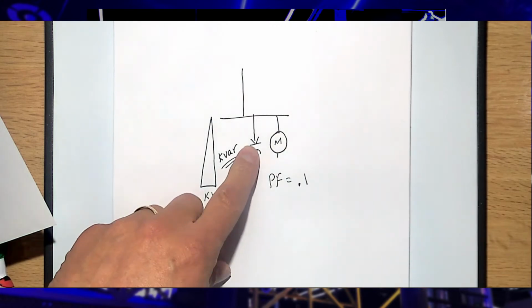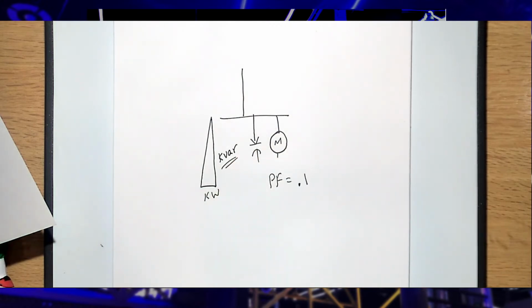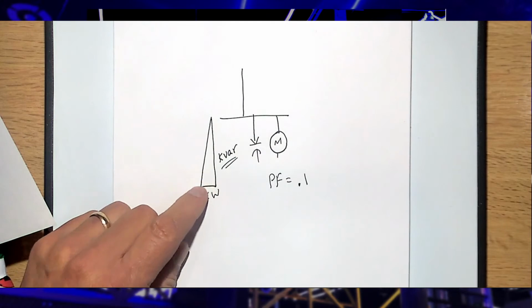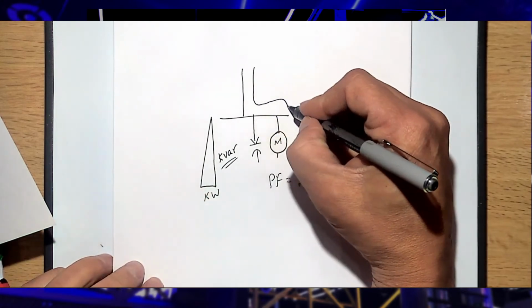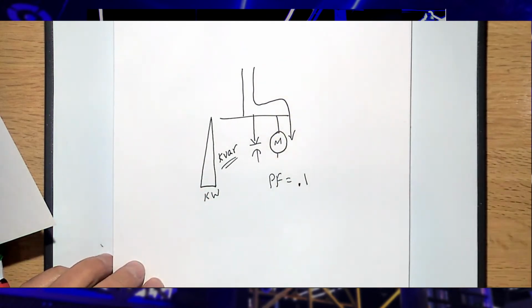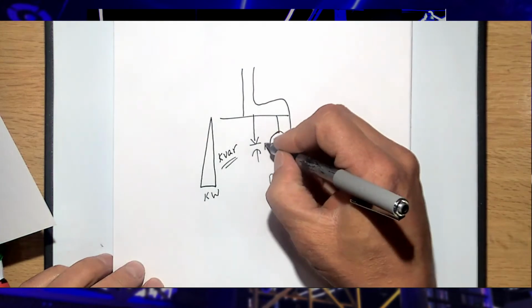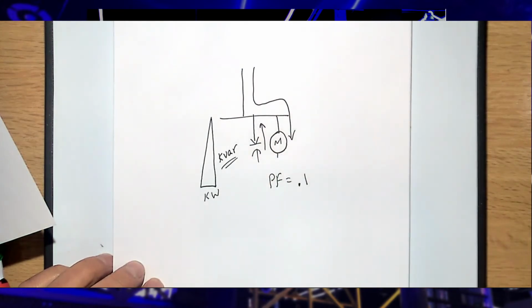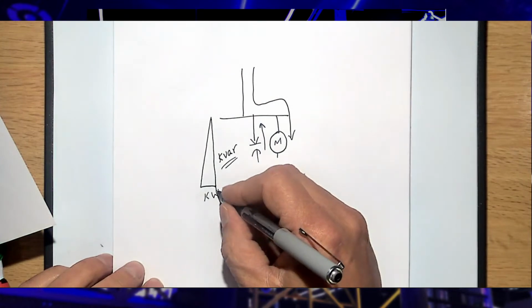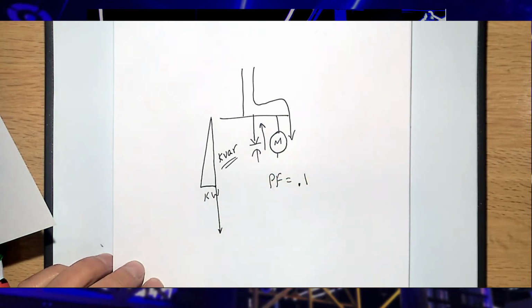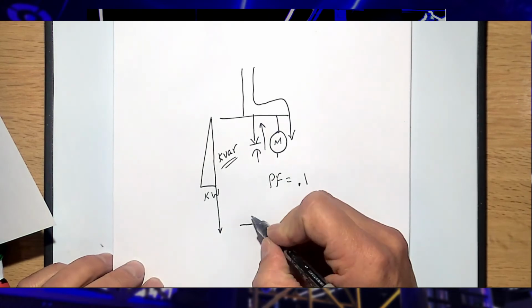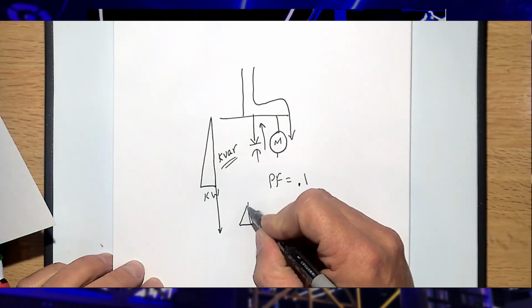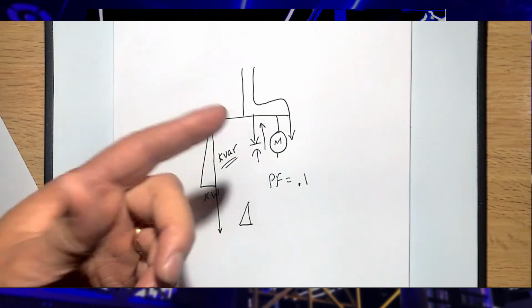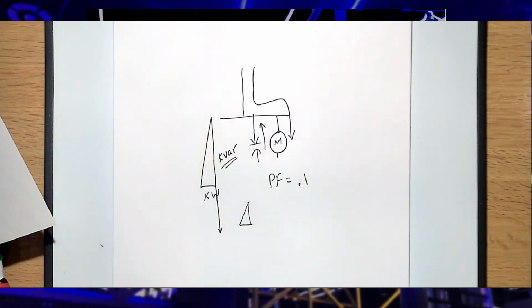So now, if I put a capacitor on, and I hang a capacitor right here, and turn it on, what have I done? Initially I have watts and VARs coming that way. Now I have VARs that are kind of equal and opposite of the motor. So if I put a capacitor on that's equal and opposite of the motor, look at my resulting power triangle. Still has a little bit of kilowatts, but maybe the kVAR is like this. So maybe I've negated 2/3 of the kVAR.